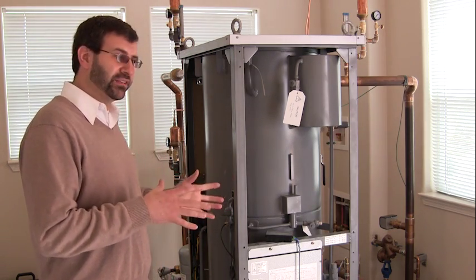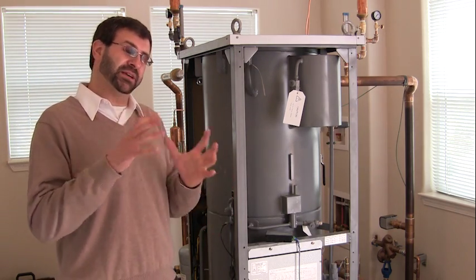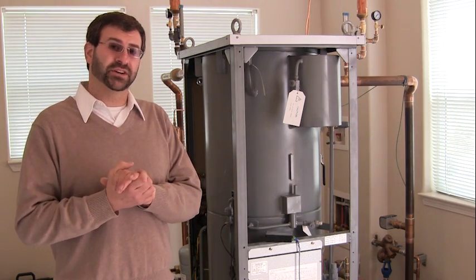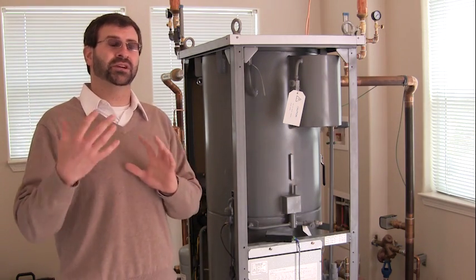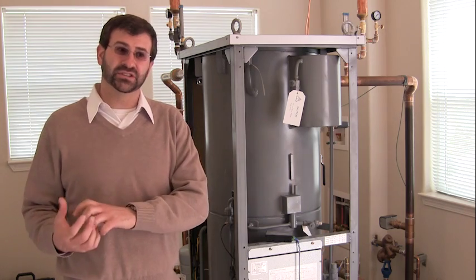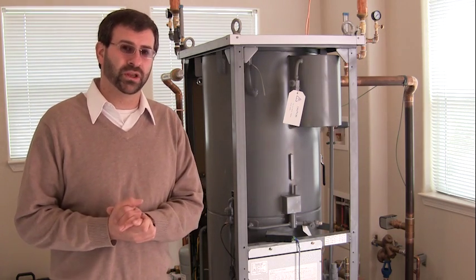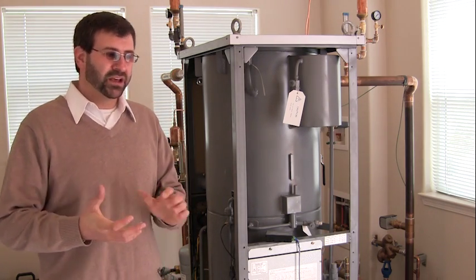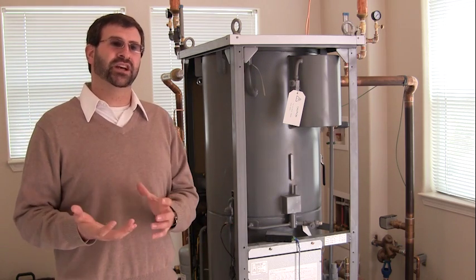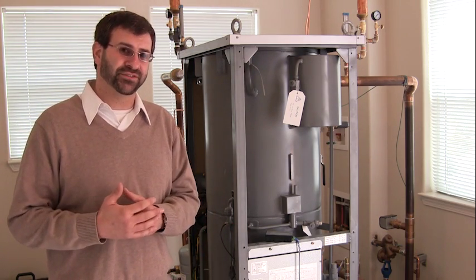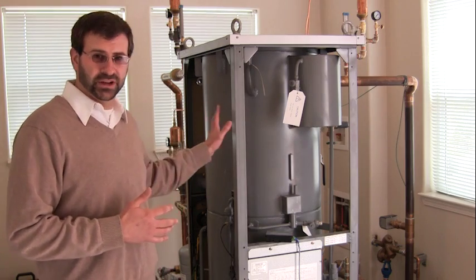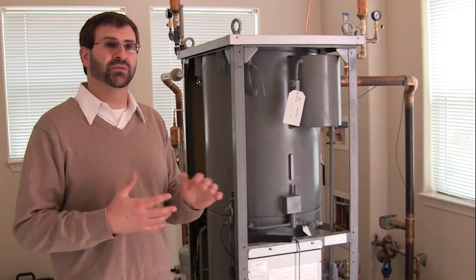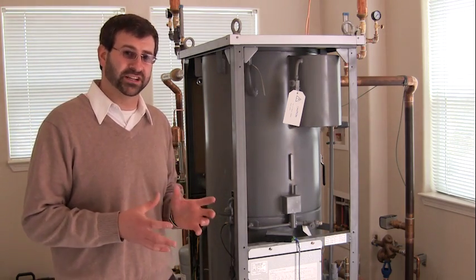So what we do with this is that refrigerant can be absorbed in the water, transferred over to the heat exchanger to be cooled, and then it can be used to take the energy out of cooling water that's being used. The bottom line is if we can generate solar hot water at 150 degrees, with this unit we can generate cold water between 42 and 45 degrees.